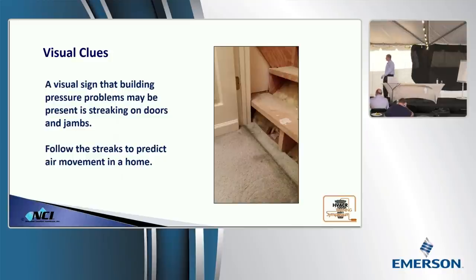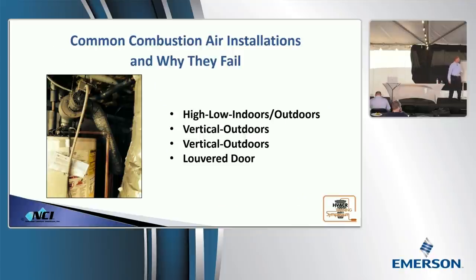There's also building clues. You guys ever seen carpet discoloration around doors? Spider webs? It's a wall-to-wall filter. That's a sign that air is moving underneath that door, and you're seeing the carpet filter that air as it's moving. So you can actually do a pressure test. Where's Steve Rogers at? I know they sell some instruments that do that. So you guys can actually measure that. Now, these telltale signs are telling you that air is moving. You won't know how much or which direction until you start to measure. So we've got to do that through our measurements.